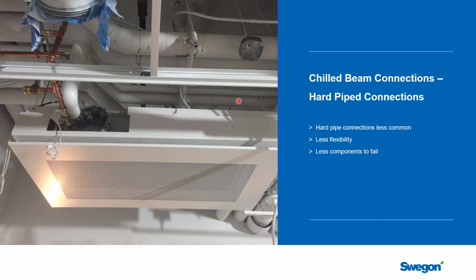We talked about flexible hoses, but on some projects you'll see hard connections. You can see this chill beam is actually an exposed style chill beam. It's in a finished cabinet. It's not going to be moving. And in this case, the consulting engineer called out that they be hard piped. It's one less thing that could go wrong. I wouldn't necessarily describe a hose as a weak point, but it is one more thing in a water-based system that could give you trouble. And so you can see that they are hard piped.